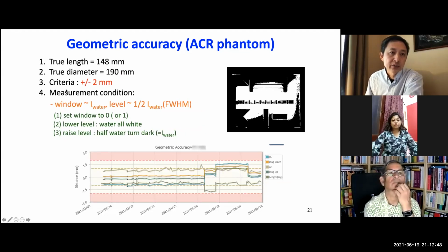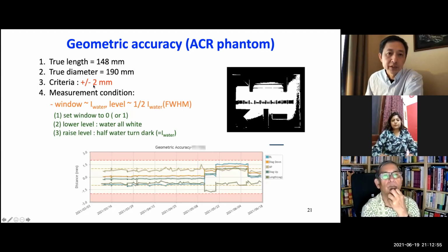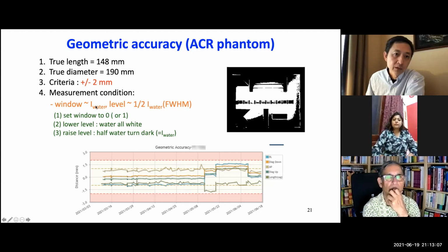So the ACR criterion is plus or minus 2 millimeters for each of those measurements. And the measurement will also depend on window width and window level. So ACR requires the measurement to be made with this setting: the window width should be about the average signal of the water, and the window level should be half of the average signal of water, which means we are measuring at the full width at half maximum.